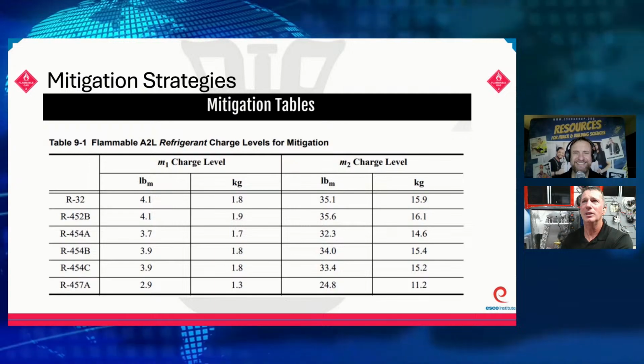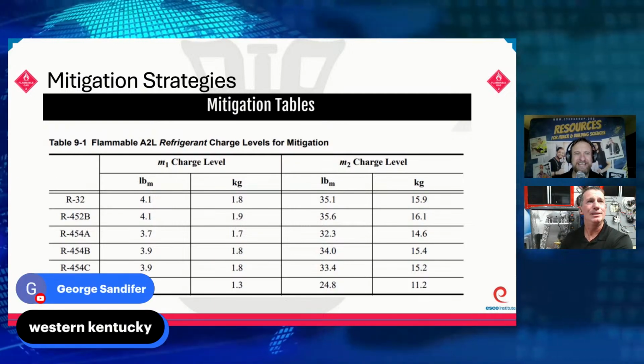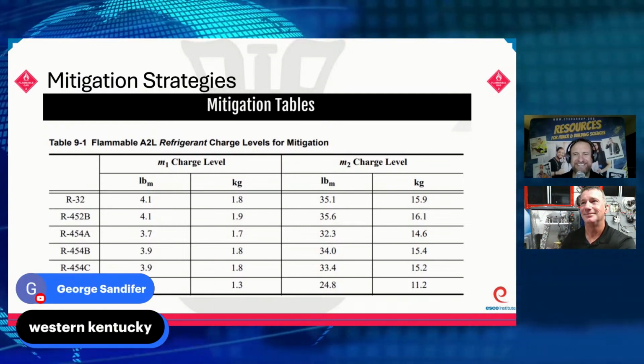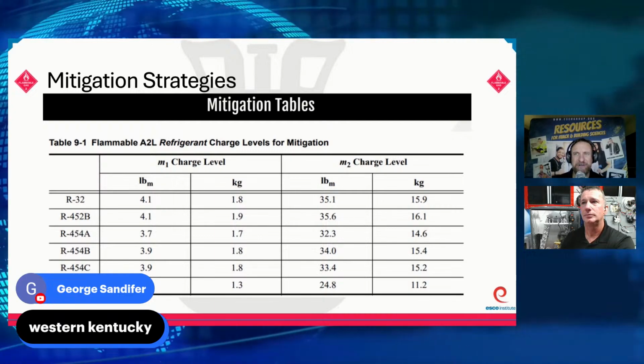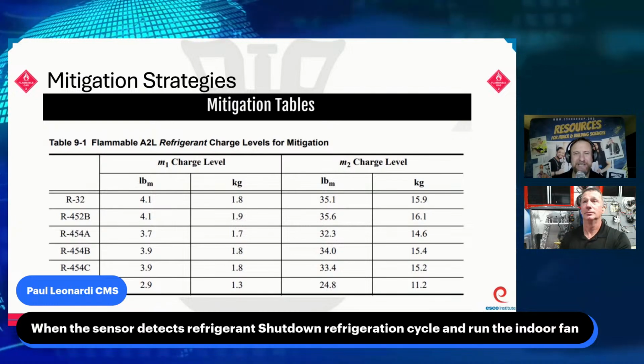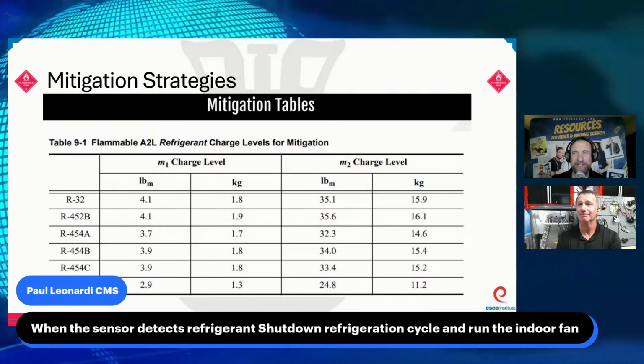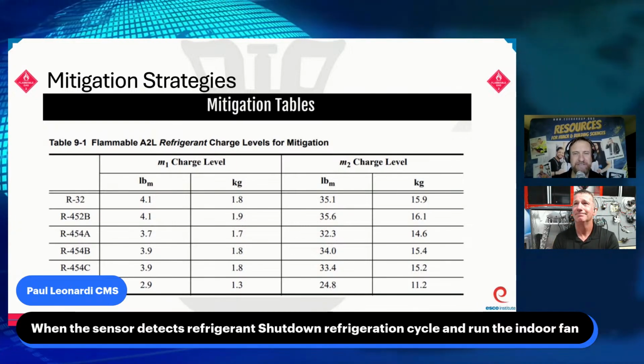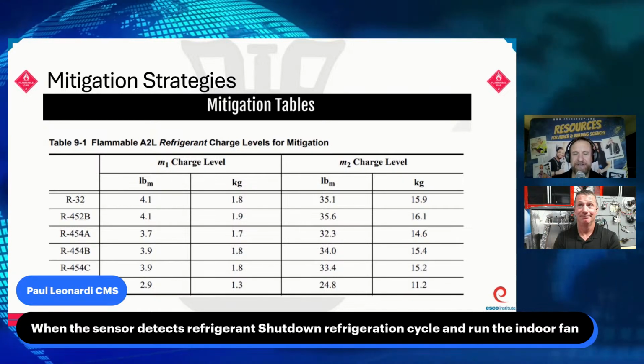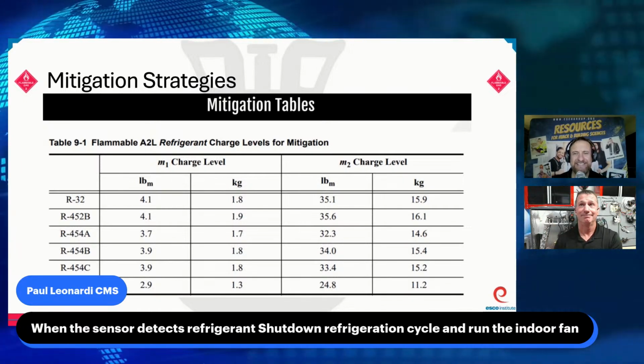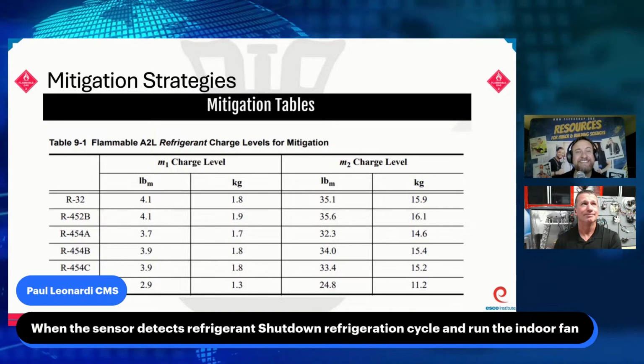Let's think about that for a minute. Yep, you would need an interface in there. And there's two things we're going to do. One, we want to shut off the call for heating so that we shut down any potential for a flame, an ignition source. So we want to shut off our W wire, so that we don't have the gas valve dumping gas in there, and then we'll let its existing mitigation take over.